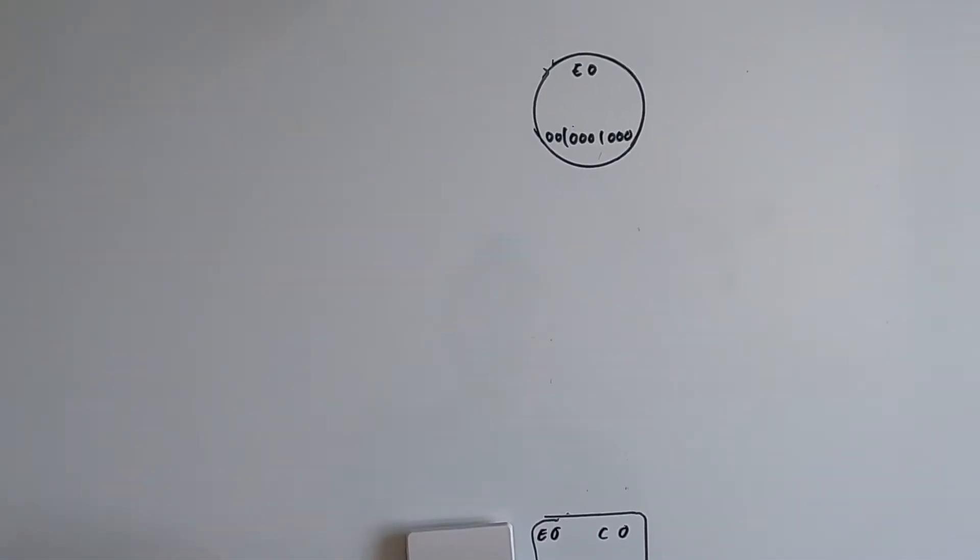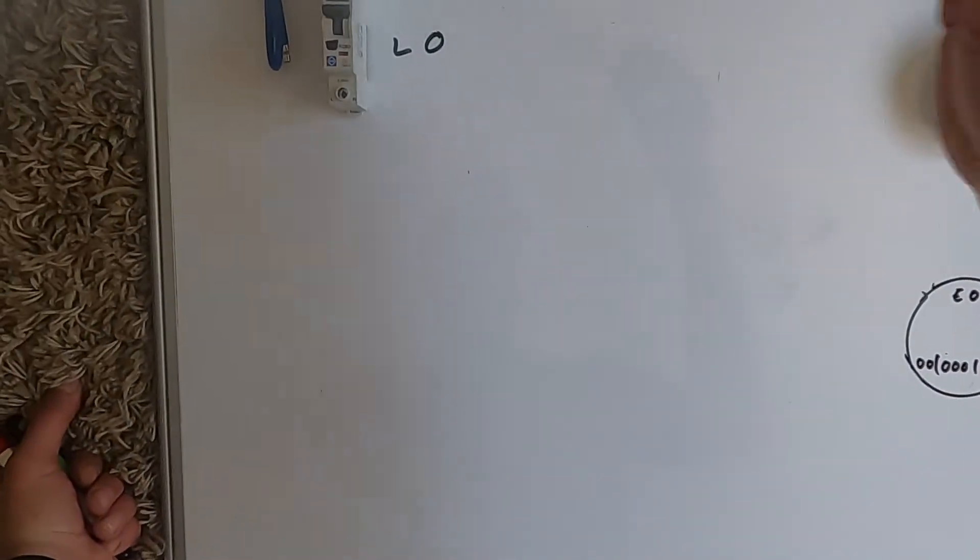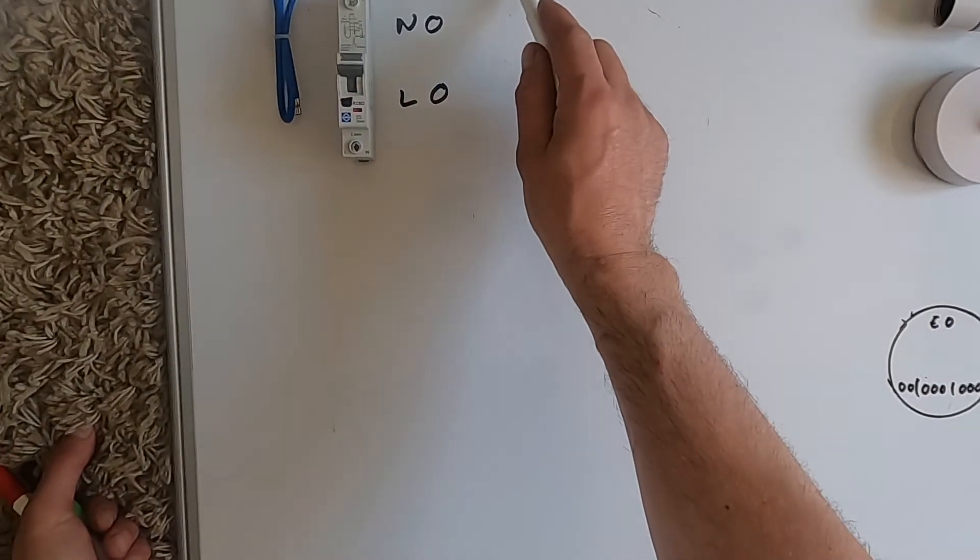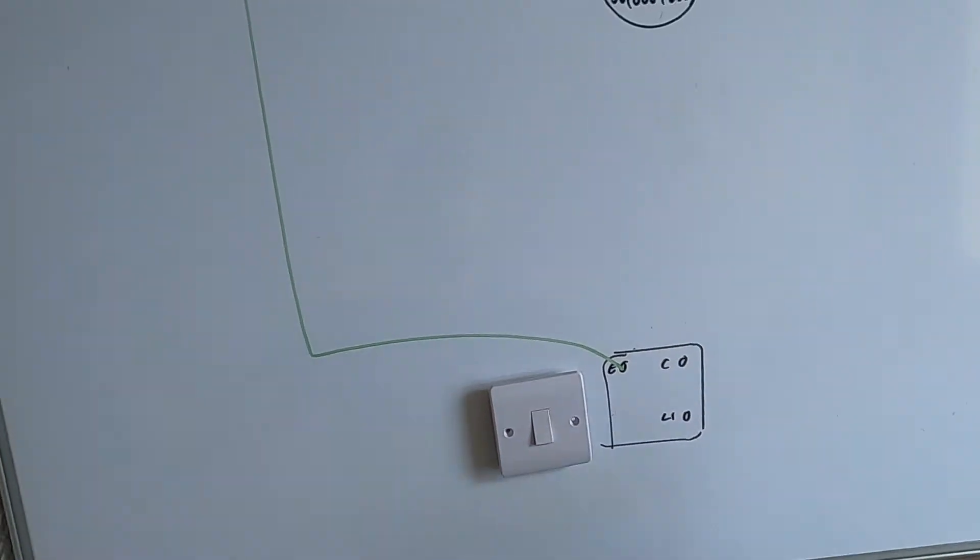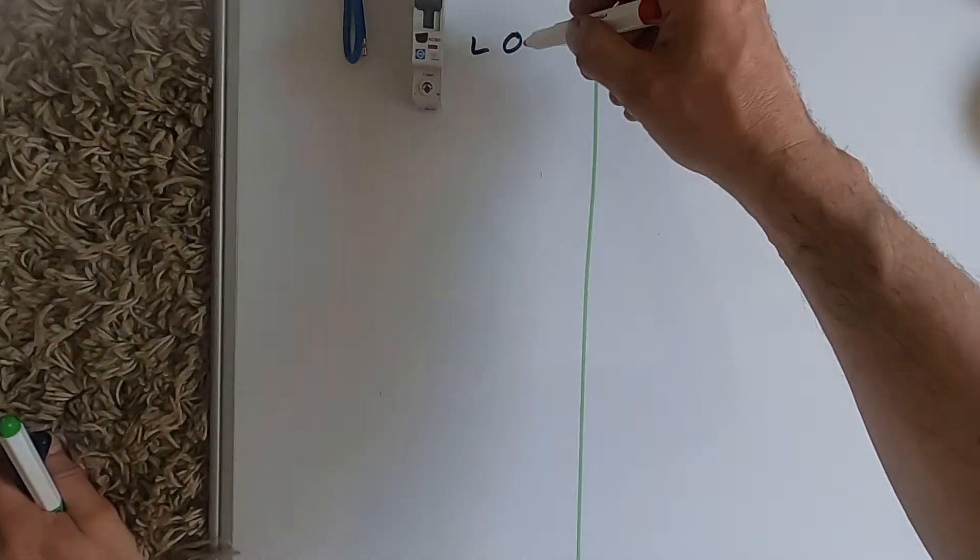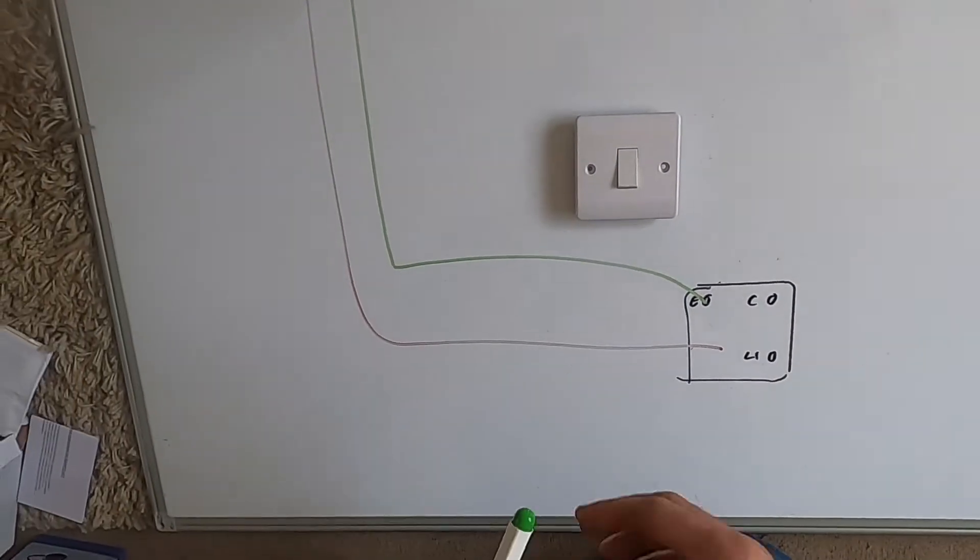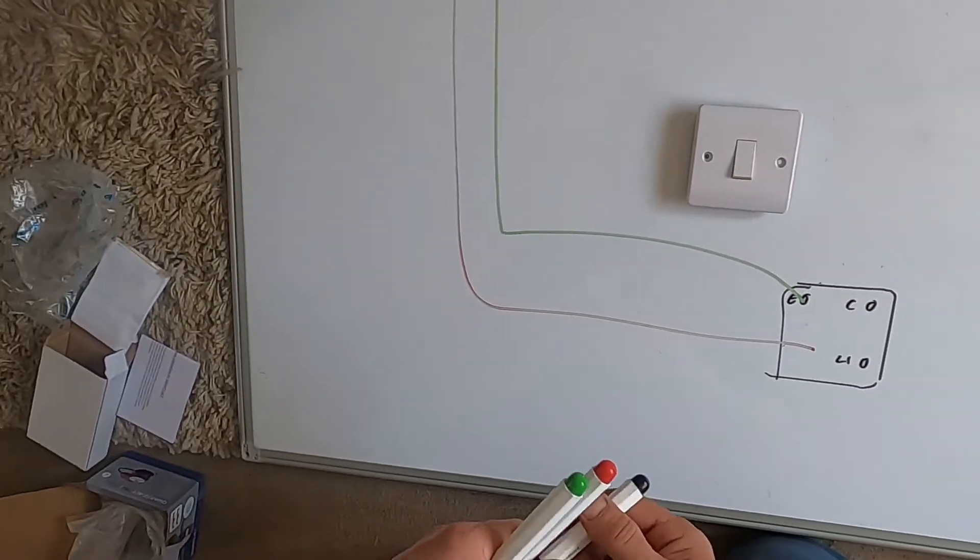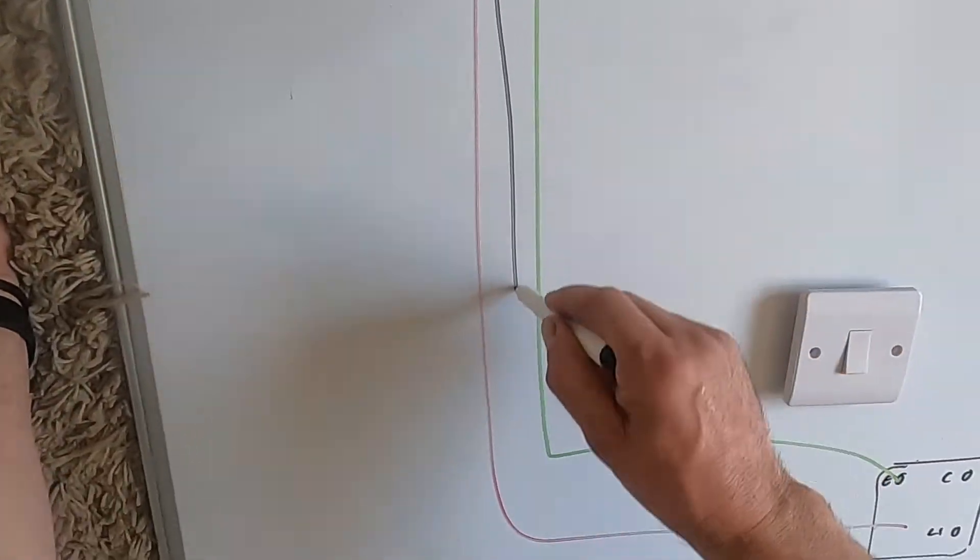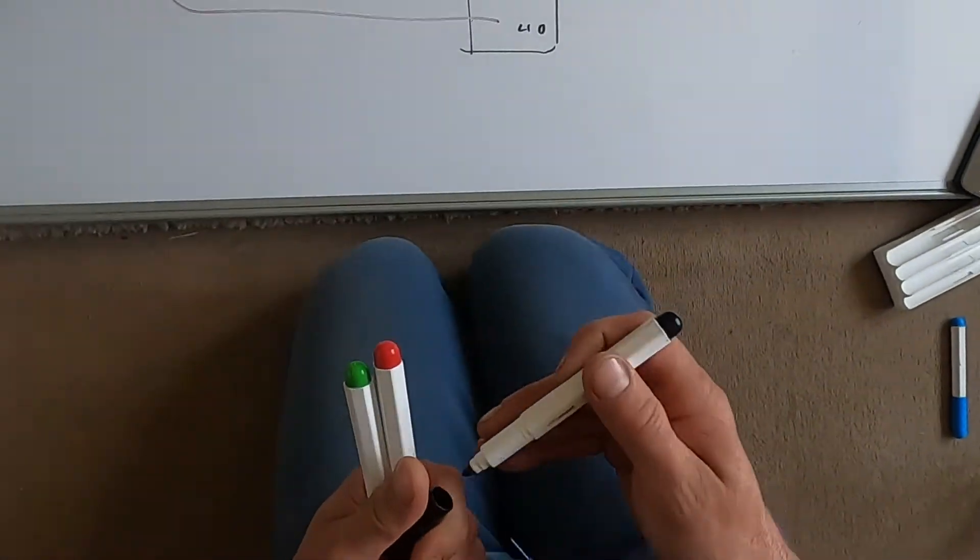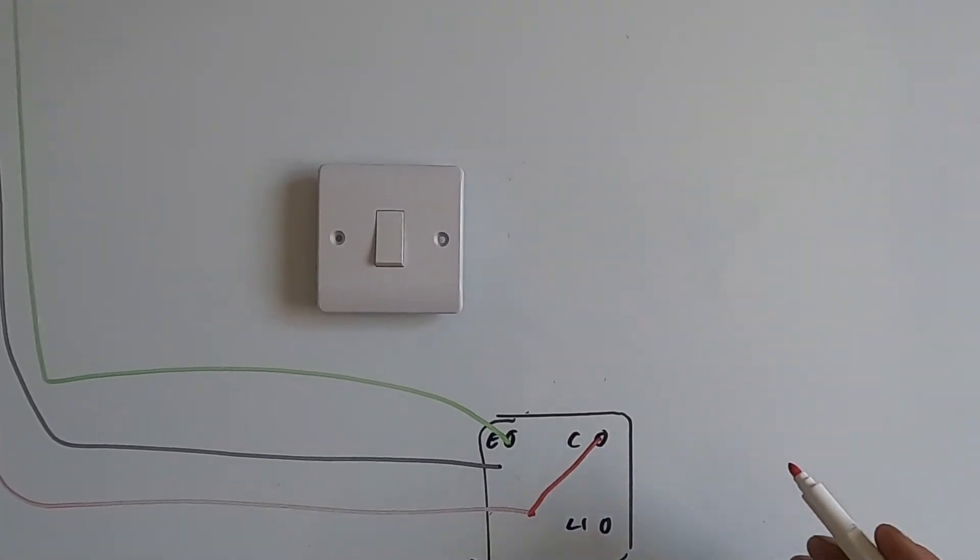So then the earth, instead of going from the light to the - instead of going to the light, go to the light switch. You take your earth to the switch like that, you take your live to the switch, and you take your neutral to the switch. And into the switch, you'll go to the common, so that's common straight away from the fuse board, so that will always be live.